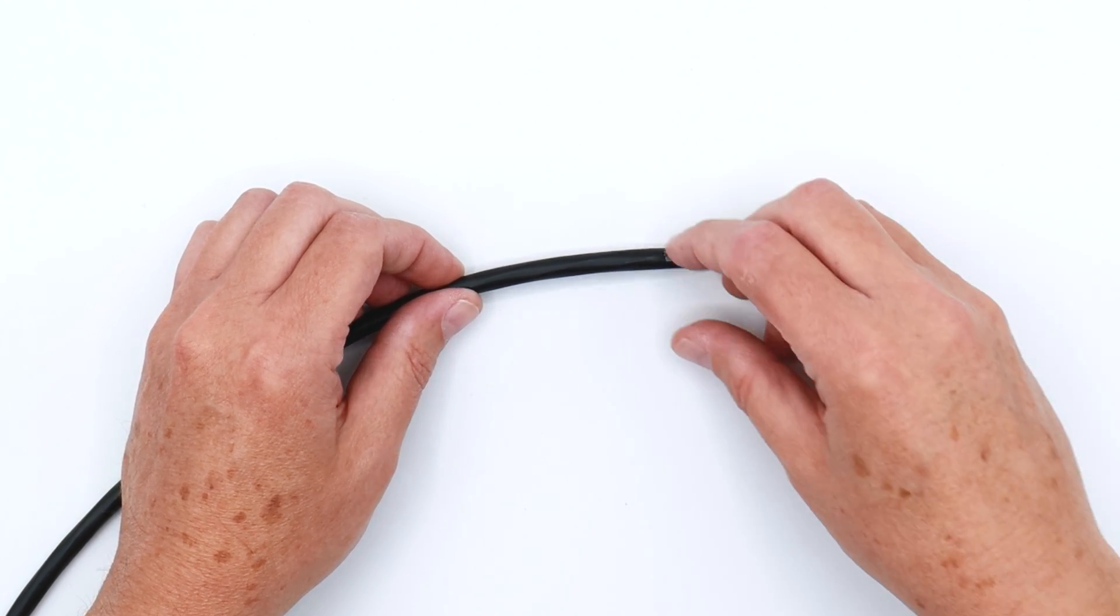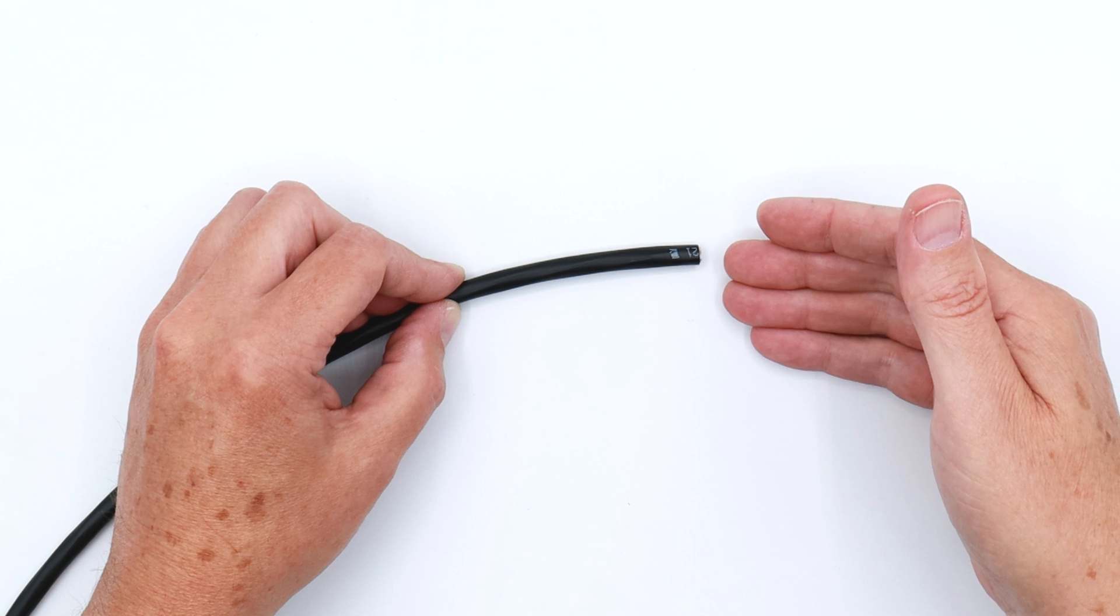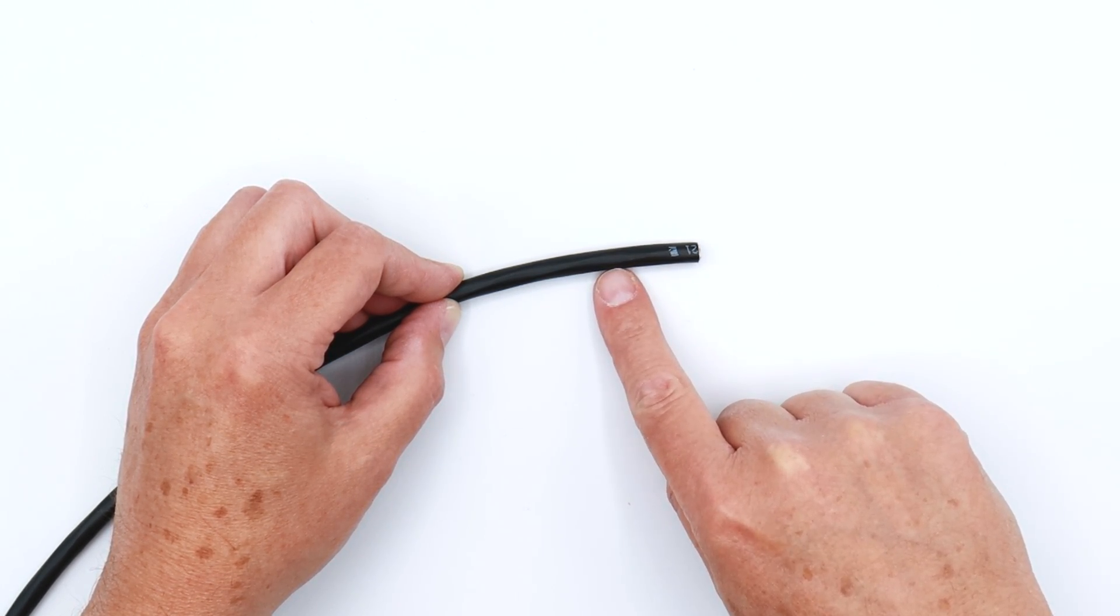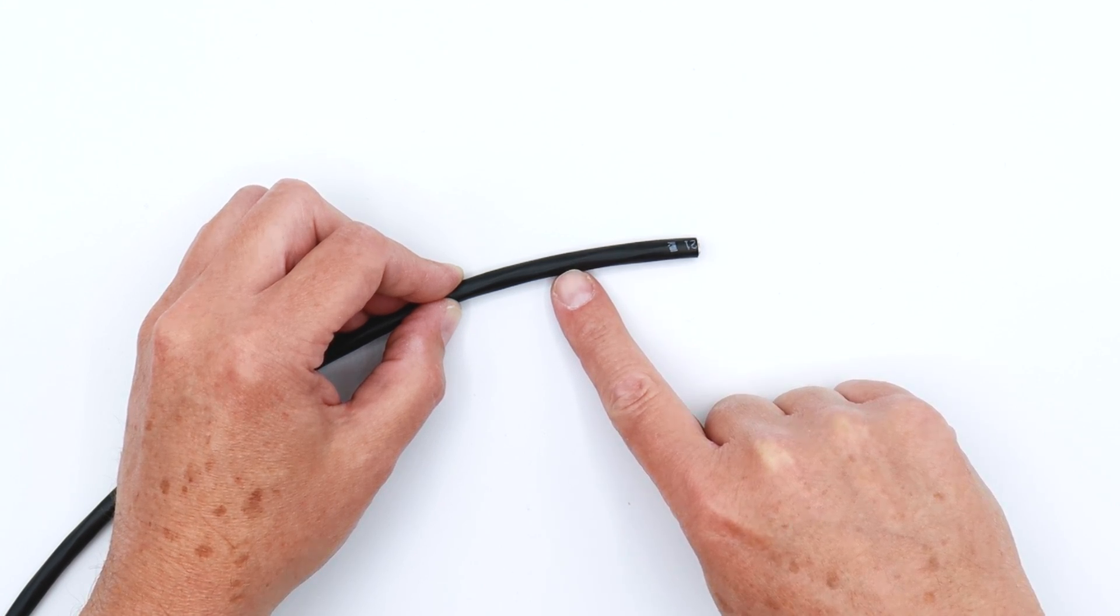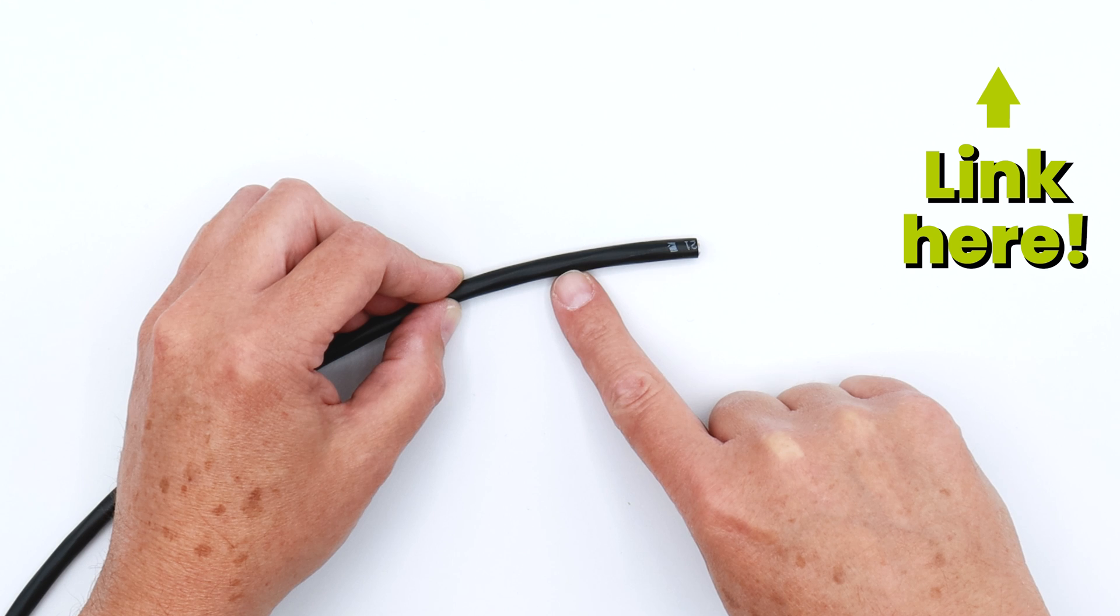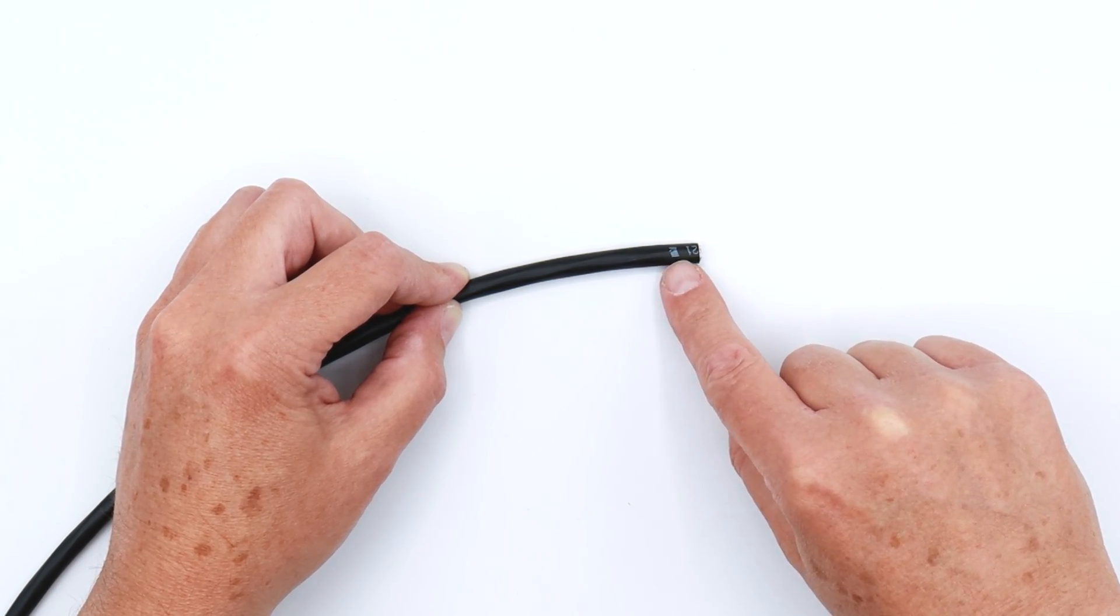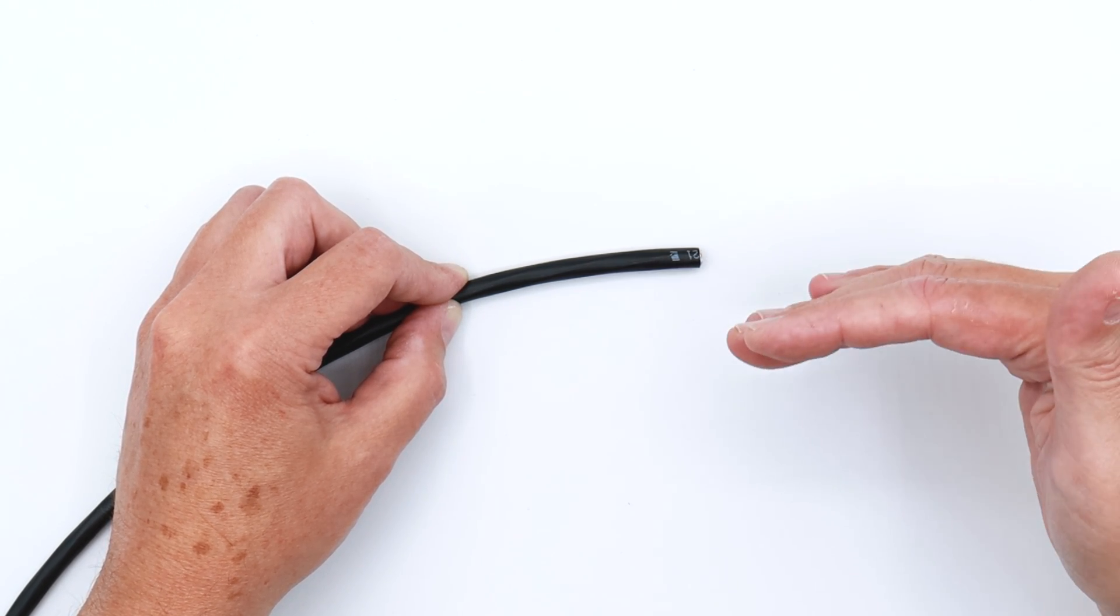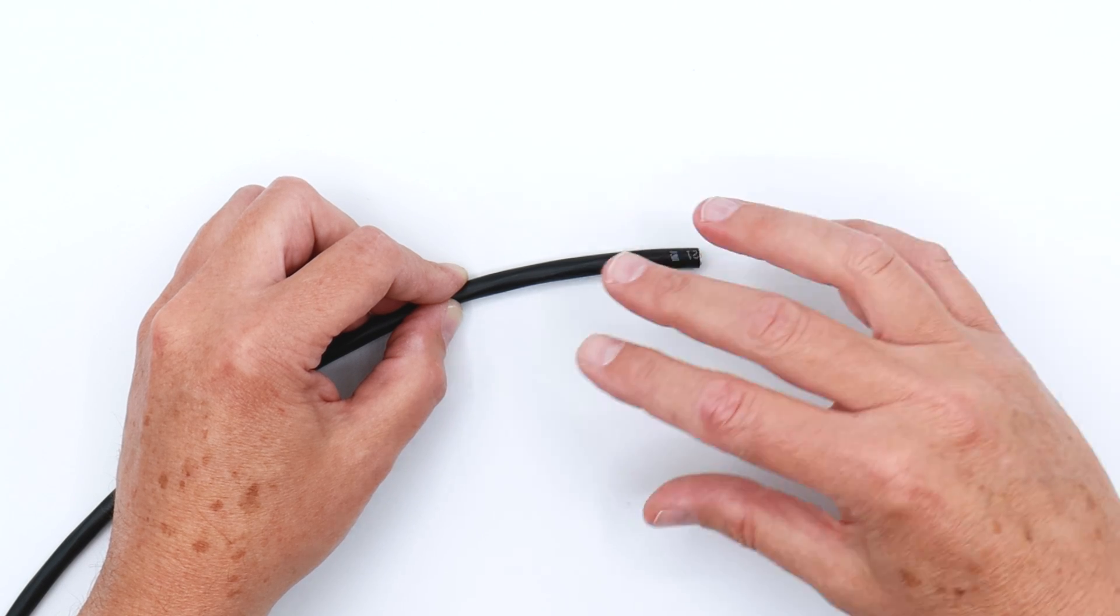As far as length is concerned, because you're going to be taking this cable outdoors. Now, you don't have to direct bury it, you can run it above ground. If you're going to be taking this cable outside, it is going to be subject to temperature extremes. And therefore, there is a temperature chart which you should reference, which will give you an idea that as ambient temperatures go up, your lengths that are permitted get shorter. So you should be aware that in an outdoor environment that your cable could be subjected to temperature extremes and may need to be shorter as a result.